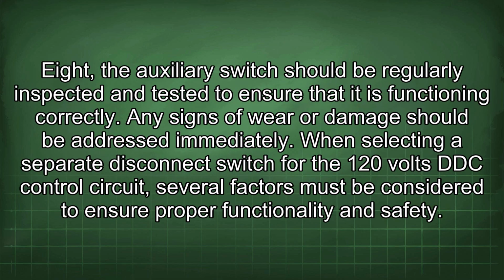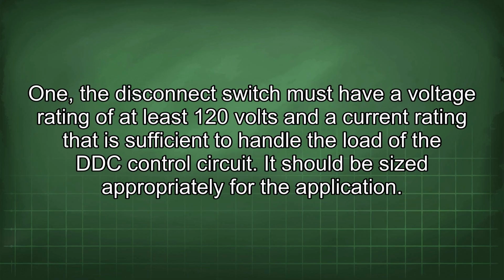8. The auxiliary switch should be regularly inspected and tested to ensure that it is functioning correctly. Any signs of wear or damage should be addressed immediately. When selecting a separate disconnect switch for the 120 volts DDC control circuit, several factors must be considered to ensure proper functionality and safety. 1. The disconnect switch must have a voltage rating of at least 120 volts and a current rating that is sufficient to handle the load of the DDC control circuit. It should be sized appropriately for the application.